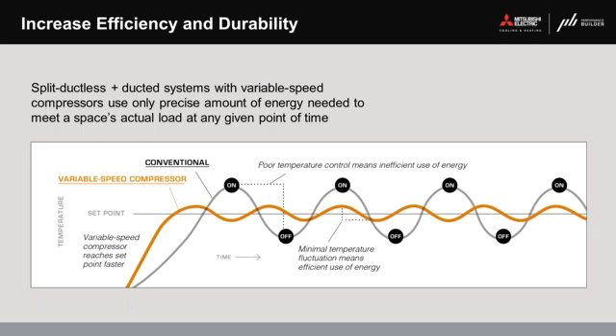Because the system can ramp up to the compressor speed needed and hover around interior set points, you might think that's harder on the system since it's operating almost continuously. But in fact, anyone who knows motors understands that it's the startup that's hardest on a machine. So by hovering around a set point, instead of cycling on and off like conventional systems typically do, it's actually much easier on the system.